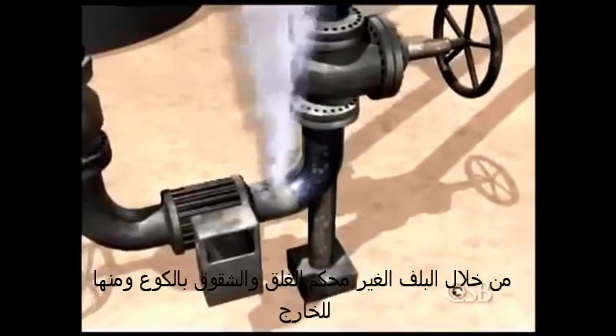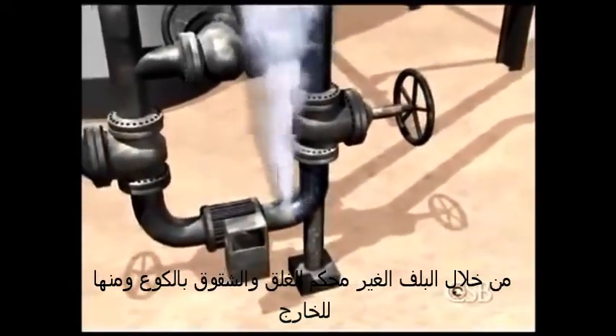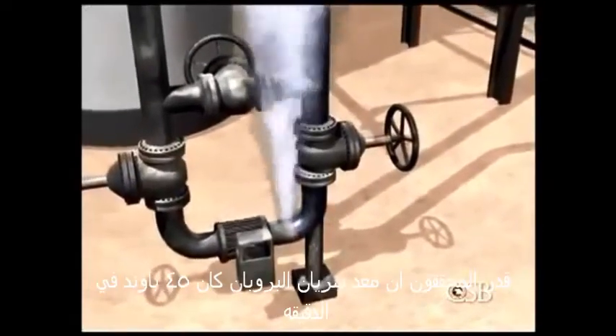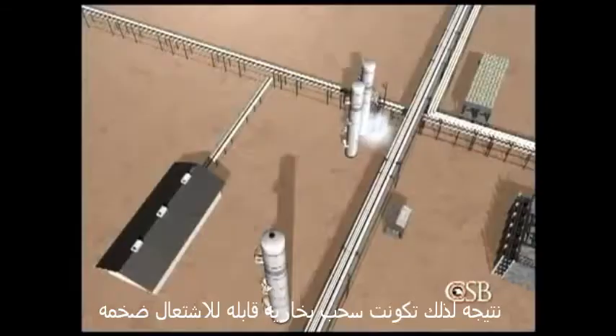High-pressure liquid propane from the deasphalting unit began to escape through the small opening in the leaking valve and out the cracked elbow. The CSB estimated the initial flow rate of propane at 4,500 pounds per minute. A large flammable vapor cloud rapidly formed.